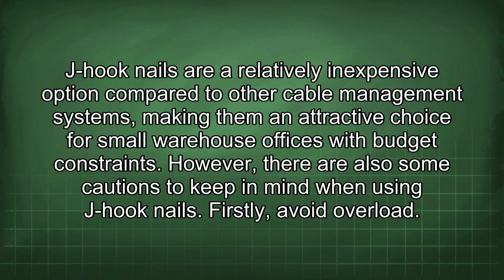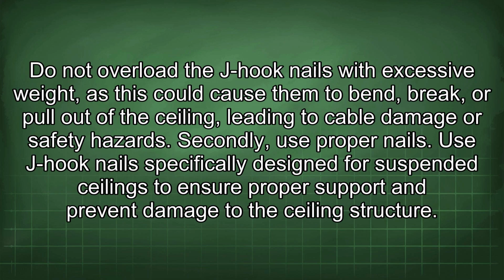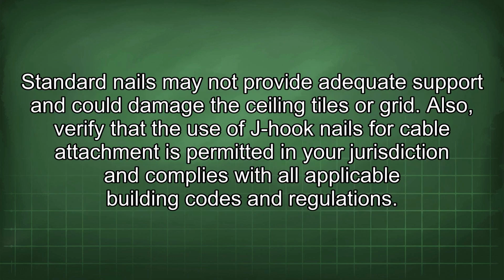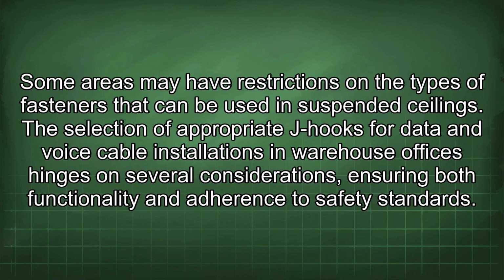However, there are also some cautions to keep in mind when using J-hook nails. Firstly, avoid overload. Do not overload the J-hook nails with excessive weight, as this could cause them to bend, break, or pull out of the ceiling, leading to cable damage or safety hazards. Secondly, use proper nails. Use J-hook nails specifically designed for suspended ceilings to ensure proper support and prevent damage to the ceiling structure. Standard nails may not provide adequate support and could damage the ceiling tiles or grid. Also, verify that the use of J-hook nails for cable attachment is permitted in your jurisdiction and complies with all applicable building codes and regulations.